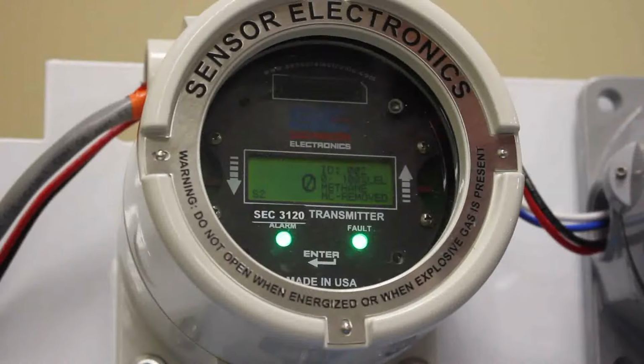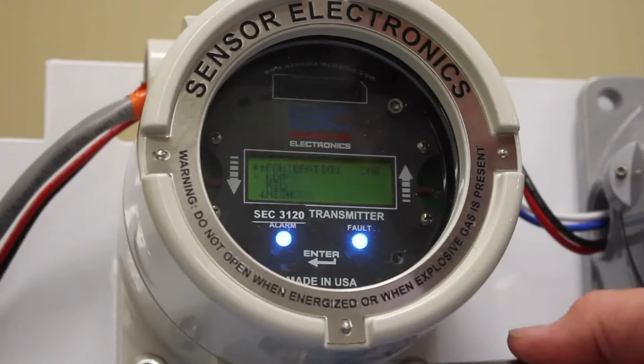What's unique about the oxygen sensor is that it trips on lowering levels, as opposed to a methane sensor. Once the gas increases to the alarm level, that's when the actual alarms would be triggered. But in oxygen, we're sensing for low oxygen concentrations. So with the oxygen sensor, you typically have to go in and set your alarm levels. And so we'll show you how to do that as well here in the same video, since it is kind of interchanged here.